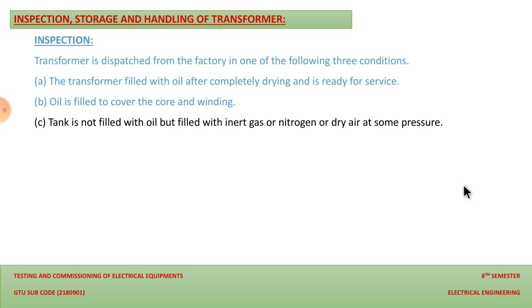Also, accessories are dispatched separately in the case of higher capacity transformers. If they are mounted on the transformer, they might get damaged during transit, so they are dispatched separately in the case of high capacity transformers. There are possibilities of damage during transit, as I have already discussed, so it should be checked for damage after receiving it. Especially the following things are to be checked, for the assurance of a proper product that you have received from the vendor.